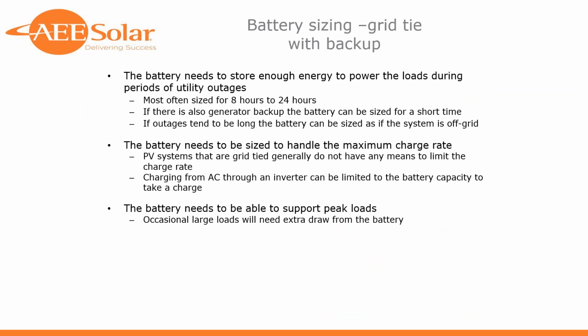Battery backup is a little more straightforward. Basically, you just need enough battery capacity to power your loads for however long you want them powered during a power outage and a utility outage. So it's more of a simple calculation. The harder part of it is to figure out what loads you want to have backed up, because batteries are fairly expensive. You do have to look and see, maybe you don't want to back up your air conditioning or your heating or your well pump if you have enough water storage to do without it.